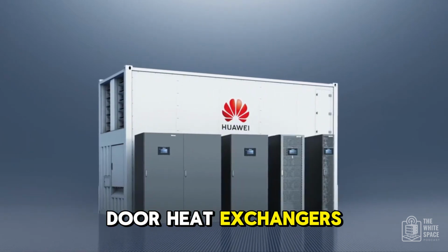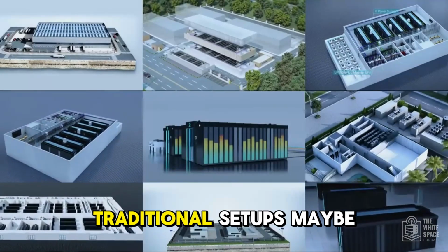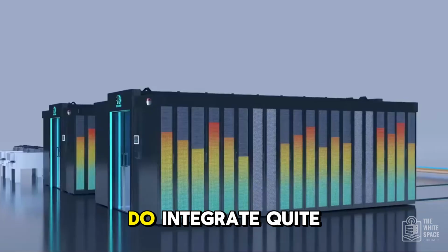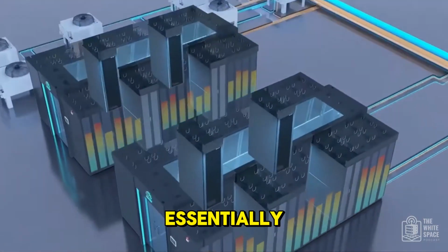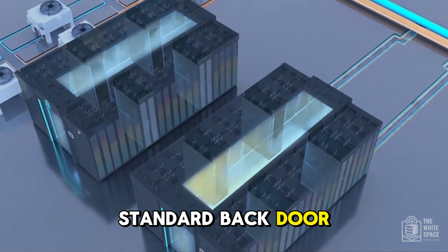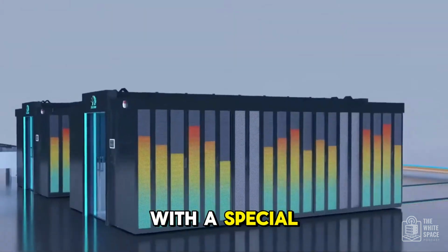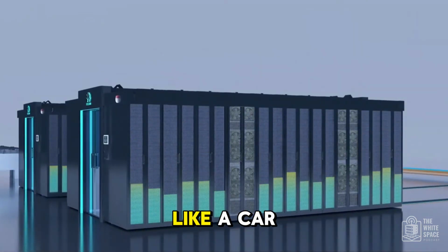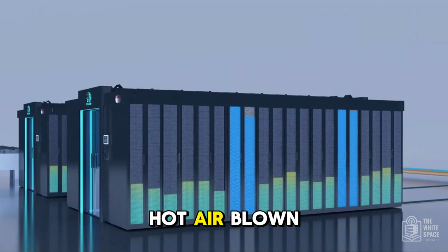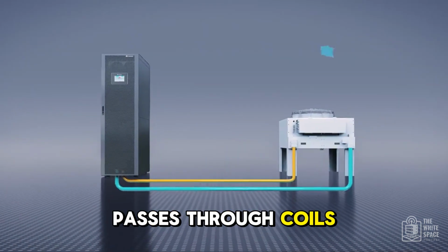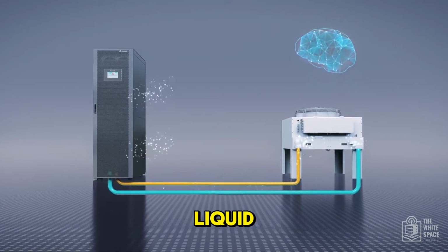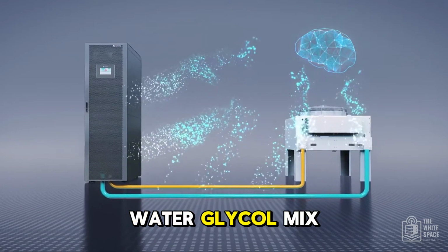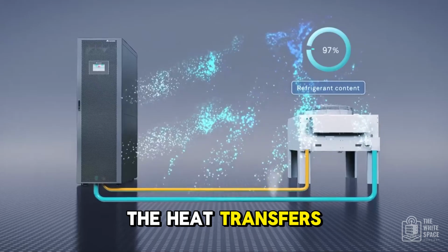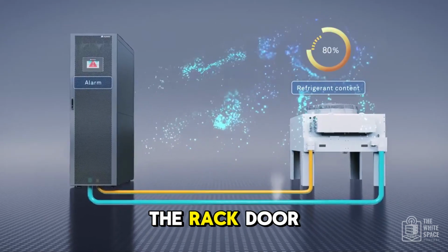Rear door heat exchangers. These sound a bit closer to traditional setups, maybe? How do they fit in? They do integrate quite neatly. Essentially, you replace the standard back door of a server rack with a special door that contains a heat exchanger, like a car radiator. Hot air blown out the back of the servers passes through coils filled with chilled liquid, usually water or a water glycol mix. The heat transfers from the air to the liquid right there at the rack door.